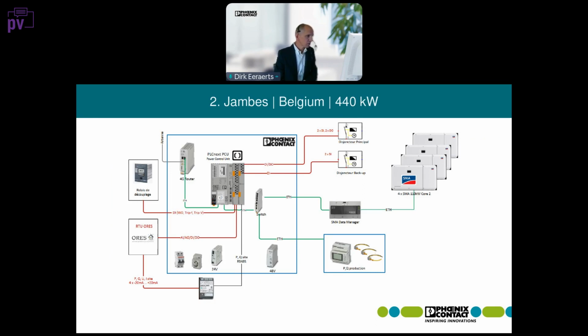Schematics of such a plant look always quite similar with small variants. So here we have a 440 kilowatt plant where we have again a cabinet with the PLC integrated. This project was executed beginning of last year, and you will see that there is quite some difference between how the DSOs communicate, and even in this particular case we see an evolution in how this DSO communicates, because initially he started with analog digital signals, and then later on he switched to Modbus over RTU. So we receive the control commands, we receive the statuses of the protection relay, we have an energy meter at the grid connection point, and also pull the P and Q of the site in.